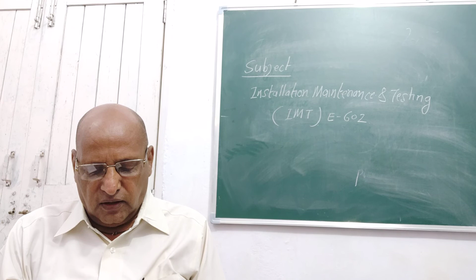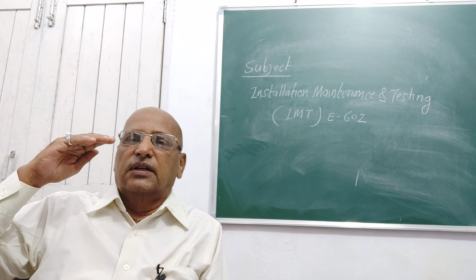Normally in a multi-storied building, heavy panels are used for giving supply to different flats, or different floors on which flats are available. So the output from the LT side of the foundation mounted transformer, we take in an LT box cubicle which is installed near the foundation of the transformer, and from there with the help of cable we take the supply up to the distribution system of the multi-storied building, which is provided at the basement, and from where we can radiate the circuits for the different storeys or different floors.